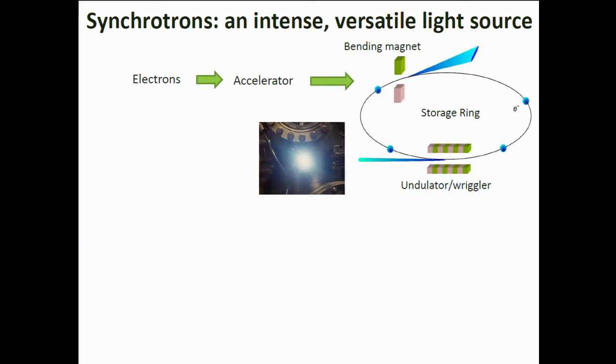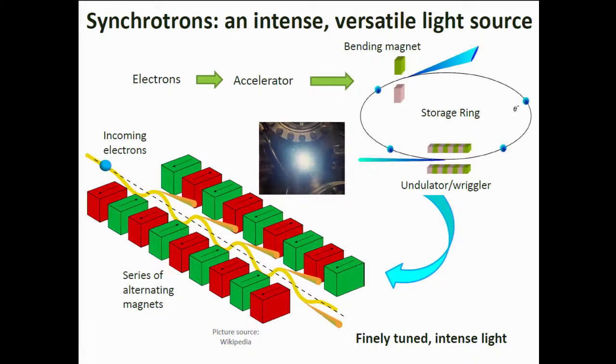Usually you would also use components such as undulators and wigglers. What these essentially are is a series of alternating magnets. Depending on the precise placement of these magnets, you can really well control small changes in the electron trajectory. This means you have much better control on the sort of light which is emitted. In this way, we can control the polarization of the light, the energy, and in effect the wavelength of the light. So you can tune this depending on what kind of sample you're looking at and what kind of information you want to obtain.